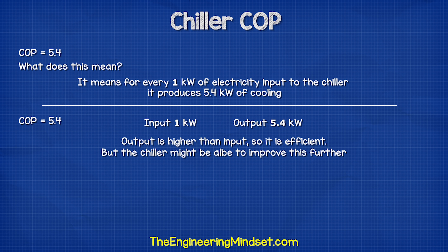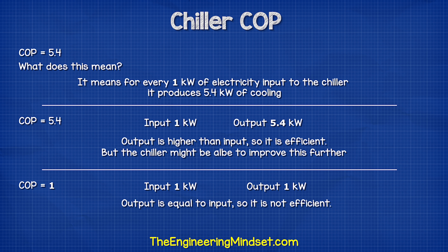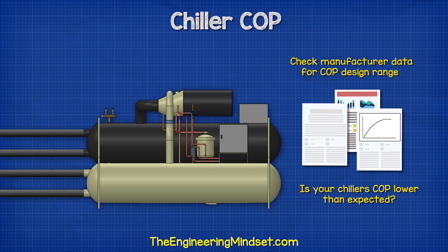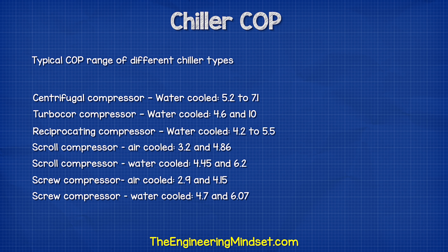We are therefore producing more cooling energy than electricity input, so it is efficient. However, this might not be operating at optimal performance and we could improve this. If we had a COP of 1, that would not be good because it means we would only get 1 kilowatt of cooling per 1 kilowatt of electricity. You can check with your chiller manufacturer what the design COP range is for your model to understand if it is operating efficiently. Typically, chillers will fall within certain ranges depending on the type of compressor used.